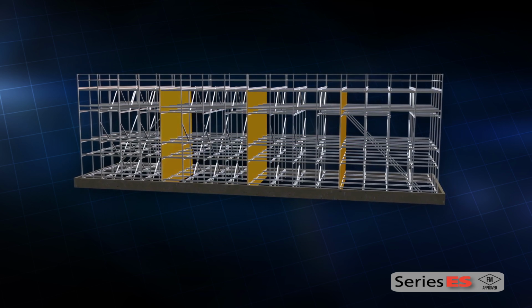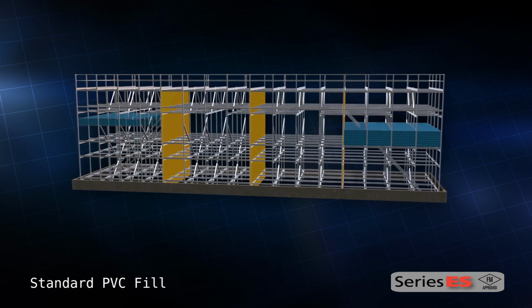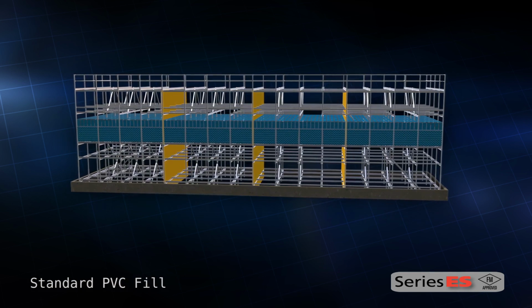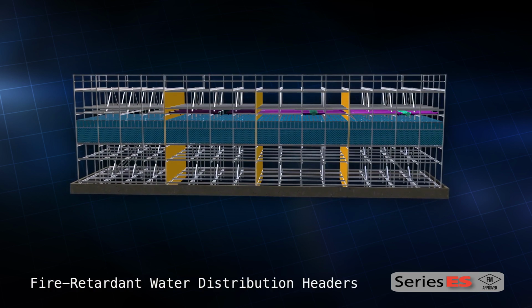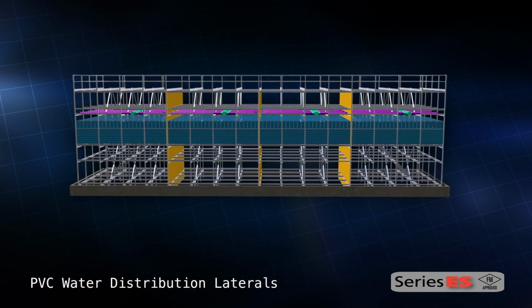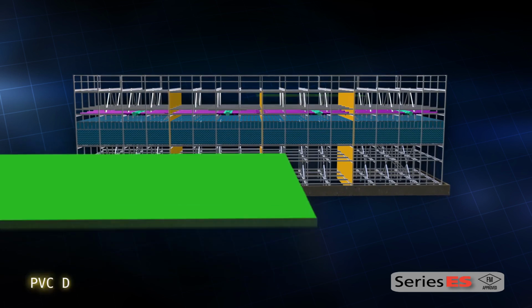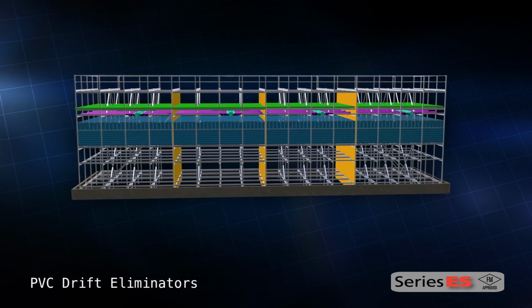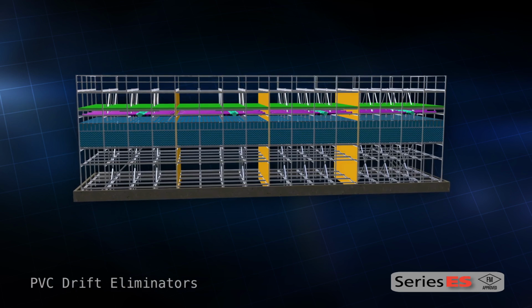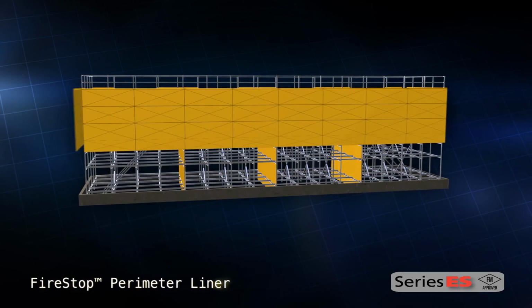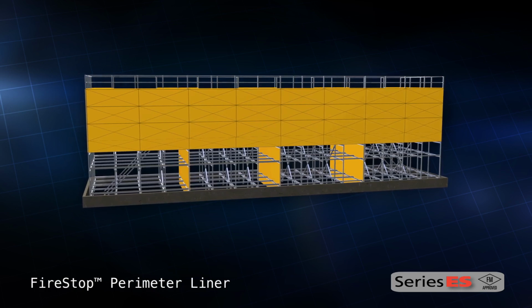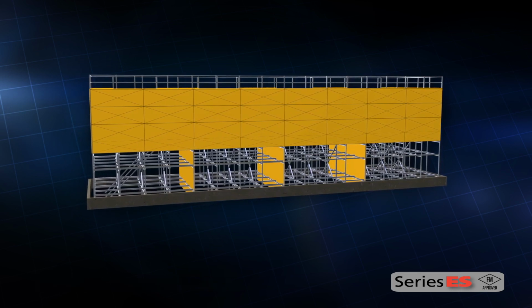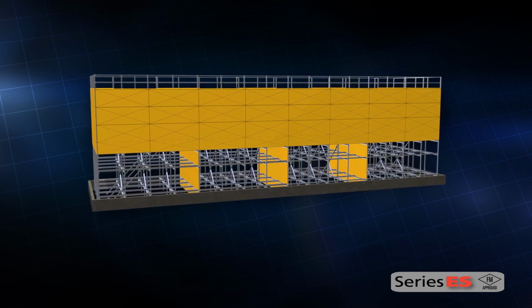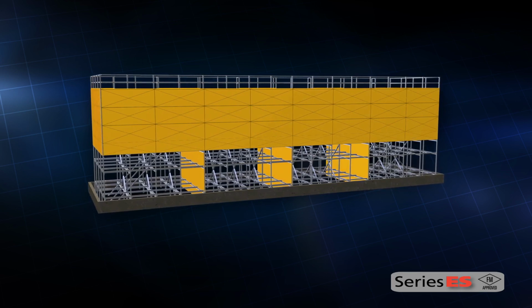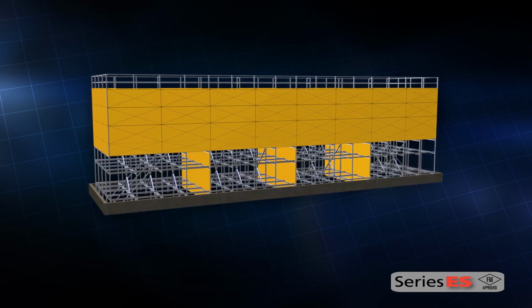The ES cooling tower is provided with standard PVC fill, and its water distribution system is constructed of fire-retardant headers and PVC laterals. PVC drift eliminators are positioned above the distribution piping. The tower is then encased on 4 sides with a layer of FireStop reinforced concrete panels that create a liner around the tower perimeter. The FireStop liner and partitions contain the fire to its cell of origin.